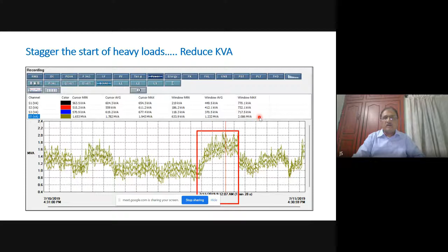So if we know how to stagger this load, 15 minutes is the integration period. If we know how to stagger this load and minimize the demand, we would have probably, optimally paid for the demand charges. So this is one sample which I thought I will share in a meeting like this. For any energy auditing study, I recommend very strongly that at the main transformer incoming, whether it is a power transformer or a distribution transformer at the incomer, a 24-hour study is very important to understand the profile of the energy consumption in a typical day. And then with this information, we should call the concerned production and electrical people to sit down and understand how this can be staggered so that the demand is not registering in this fashion.